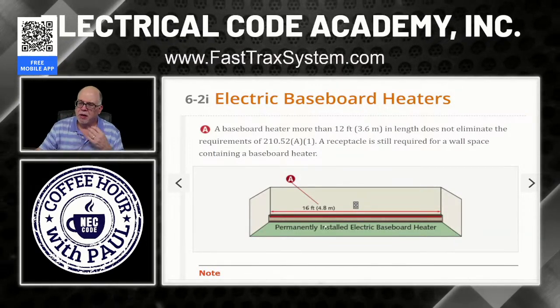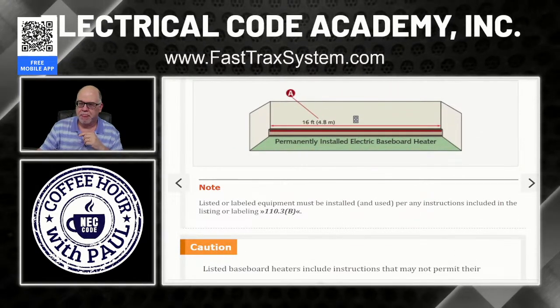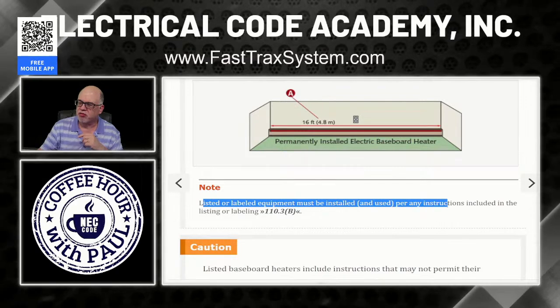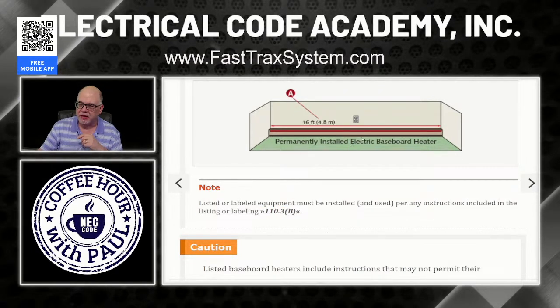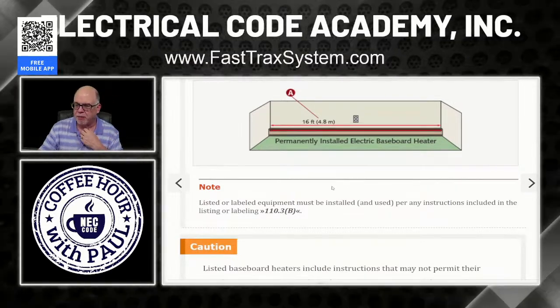But again, most of the manufacturers of these baseboard heaters will tell you, do not put a receptacle above my baseboard heater, okay? So note, listed or labeled equipment must be installed and used per any instructions included in the listing or the labeling. That's a 110.3(B). So I could buy one of these baseboards and it has a section again in the middle that may hold a receptacle, and boom, I can meet this rule and not have a problem, okay?